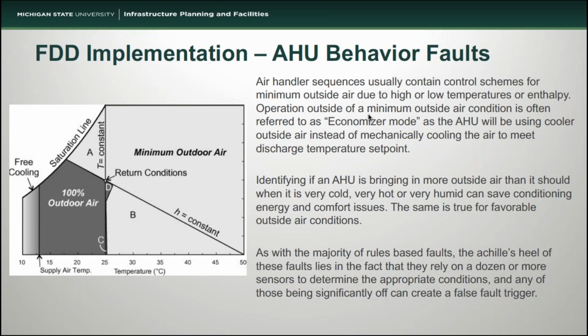Or conversely, when it's much, much warmer or much, much cooler out, we want to bring in a minimum amount of outside air so that we're not having to overcool or overheat the amount of air by bringing in outside air instead of the air that's coming back from the space. As with the majority of faults, the biggest Achilles heel of this fault is the fact that it might rely on a dozen or more sensors to determine these conditions. And so again, it's really critical that we make sure that all of these sensors are located where we think they are and that they're accurate. Next slide.